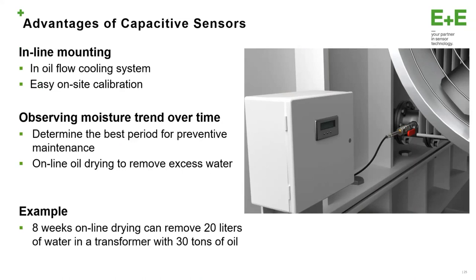The advantages of sensors placed directly in the transformers: we can choose the most interesting and representative points for sampling. A typical location is on the oil flow in the cooling system, where the temperature is very easy to monitor. Observing the moisture in oil over time, we can determine the timing for preventive maintenance. The typical maintenance to remove water — for example, with eight weeks of online drying — it's possible to remove 20 liters of water from a transformer of 30 tons.